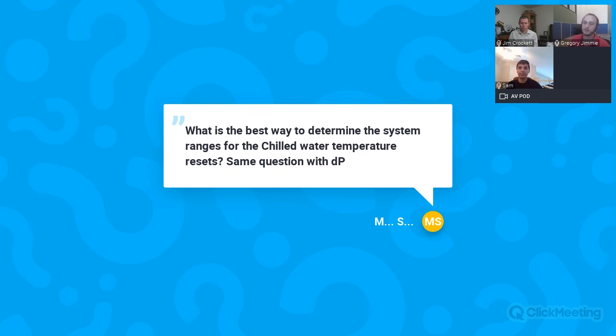Same sort of question, same sort of answer with the differential pressure. As far as your maximum pressure, again, kind of let it get to what it was designed to do. Just don't let it be there all the time. So if it was designed for 22 PSI, let that be your maximum. As far as the minimum, maybe half that. It really kind of depends on your piping and what the system requirements are.